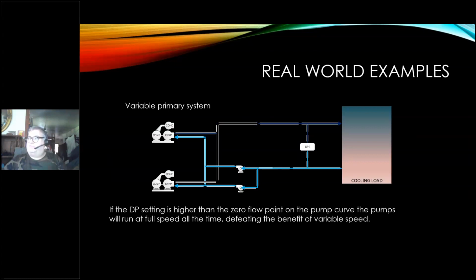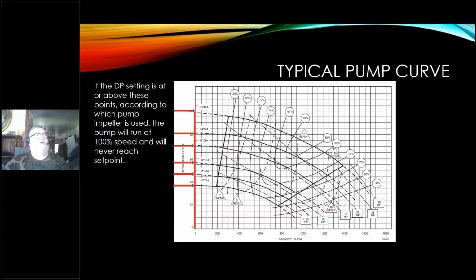Now, sometimes a TAB firm will tell you what pressure you need to operate on, but not always. So that's something you've got to watch for. If you've got like 10 air handlers being supported by this system, and you're going to see if there's any one valve that is fully open, is that what you're saying? Right. Speed up the pump if it's wide open, and if it gets satisfied and starts to close, you can slow down. So you're looking at all the valves, and you're going to pump until one of them is fully open.